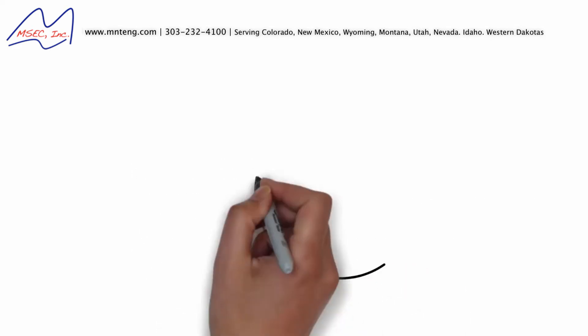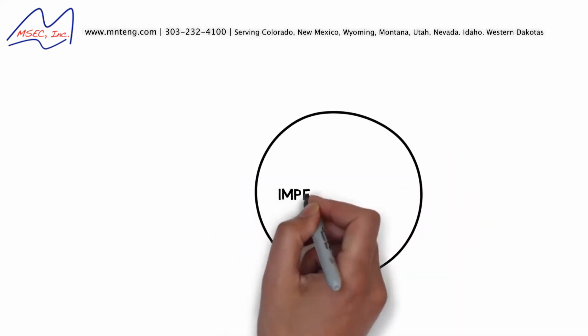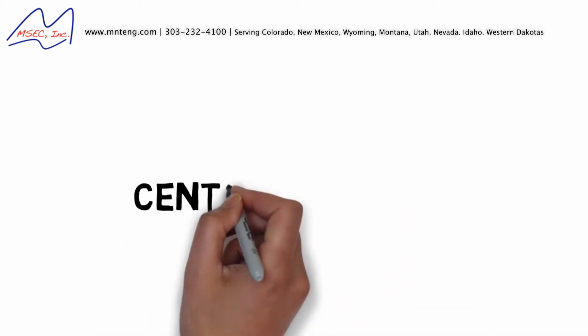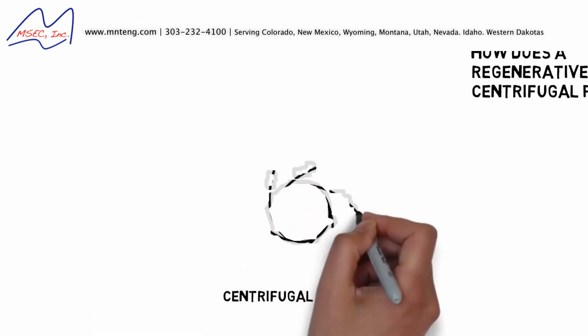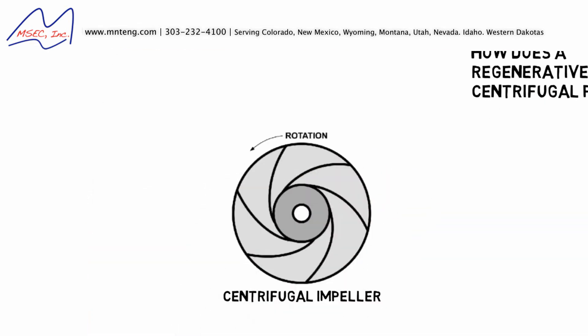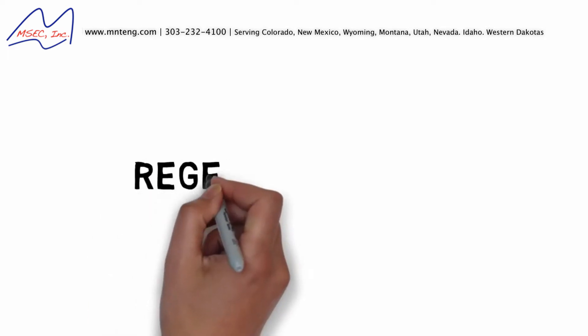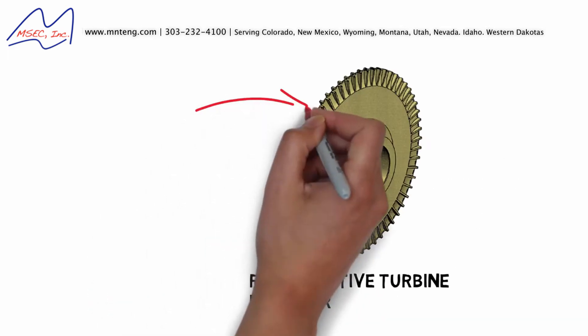The main difference between a regenerative turbine pump and a centrifugal pump is in the impeller. A standard centrifugal impeller has curved vanes that extend from the center to the edge of the impeller. The regenerative turbine impeller has rows of vanes on each side of the impeller's rim.